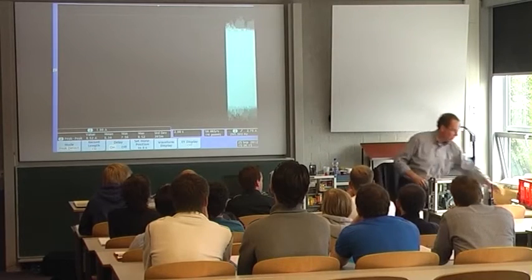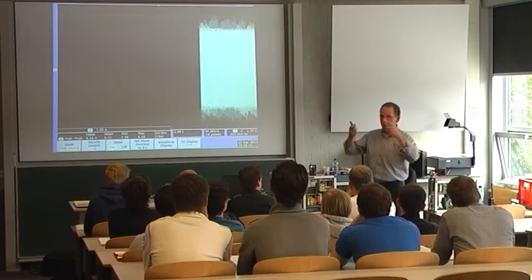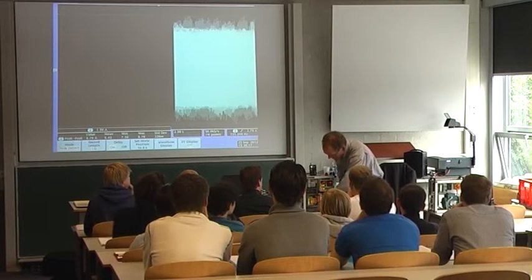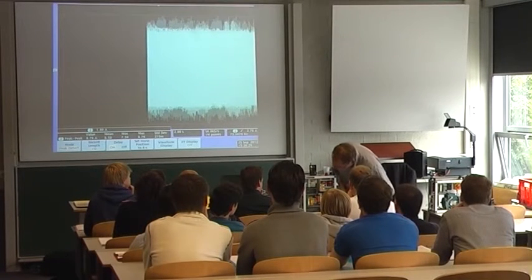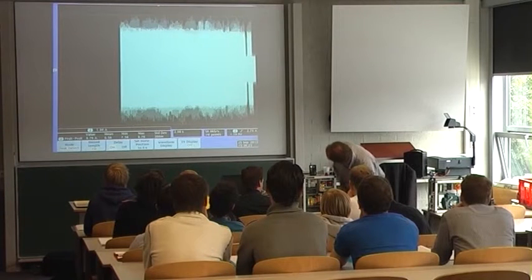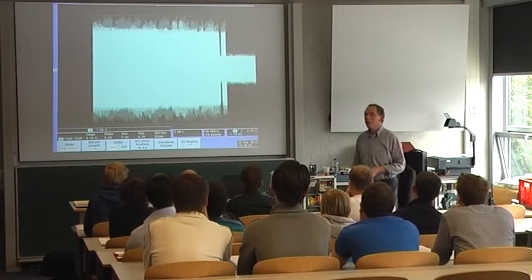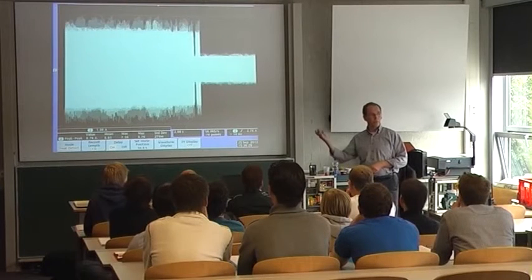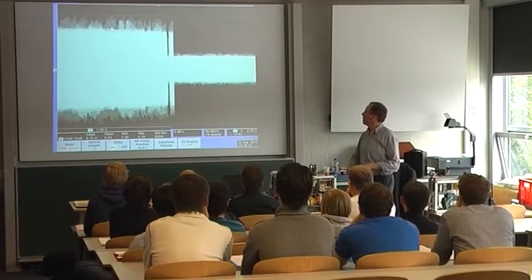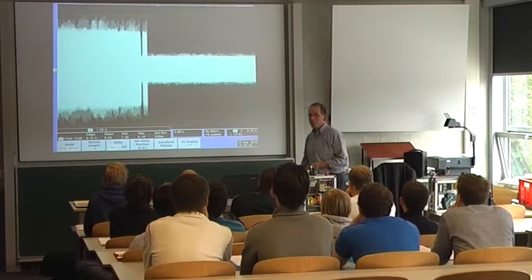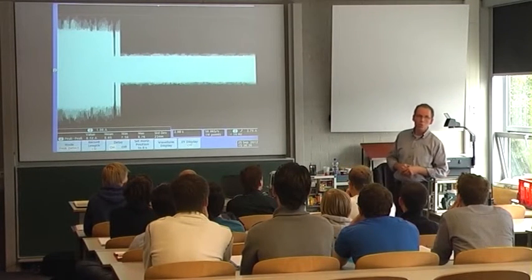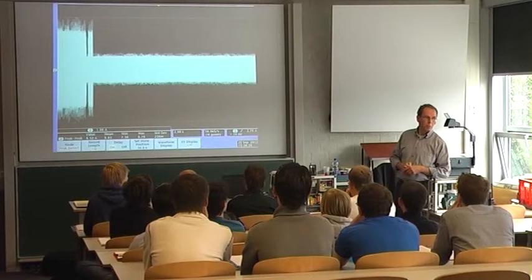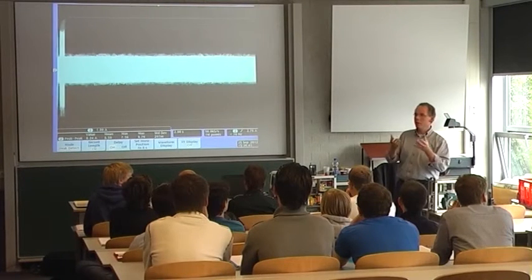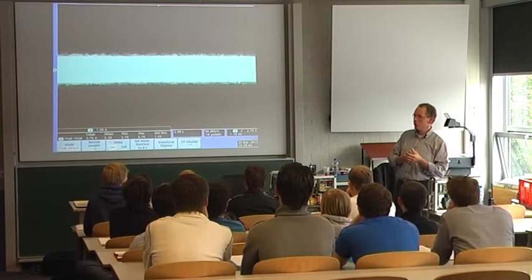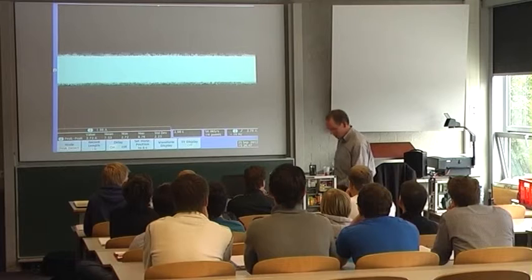That's what I'm going to do. So I will show you what happens if I connect the shield at both ends. So I'm going to connect the cable shield to the variable speed drive, or the earthing system. There it is. It's impressive, isn't it? Lots of, well, factor of 2, maybe 3. But is this the preferred practice? Is this good? Or no. Probably. Should be, well, it should be nil. Yeah? It should be 0. No leakage current.